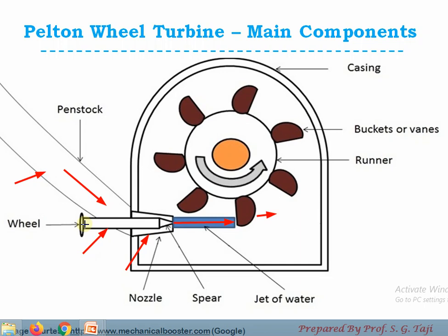The next component is the spear, also called the needle. Its function is to control the flow coming out from the nozzle — that is, controlling the discharge. If I move this needle in the forward direction, the area of the opening gets reduced and discharge coming out from the nozzle also gets reduced. If I move it in the backward direction, the flow area gets restored and discharge coming out from the nozzle also gets restored.